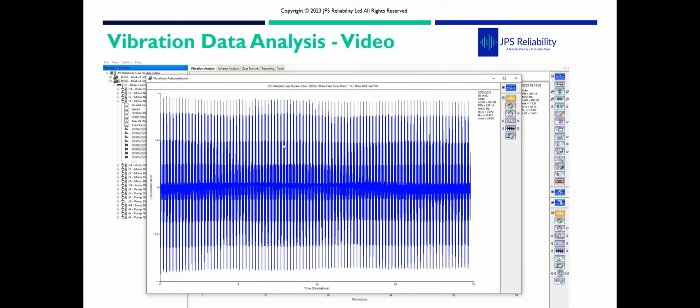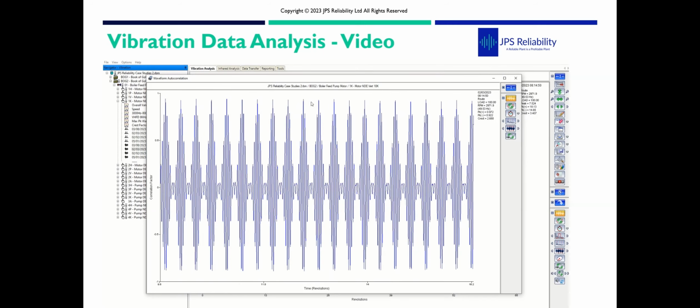You can see it looks a bit like an optical illusion. There's quite a few things going on there, but if we zoom into a small portion of it, we put our cursor on the top, jump up to top, again toggle through the fault frequencies, you can see that these pulses are bang on outer race. So outer race is screaming, but it's riding upon a really high frequency.